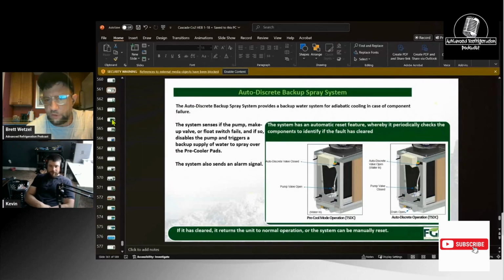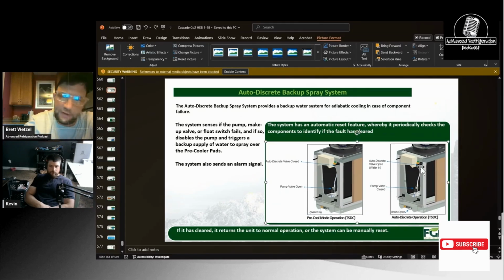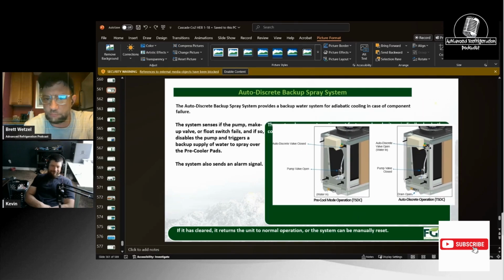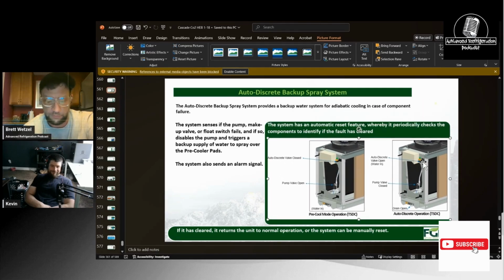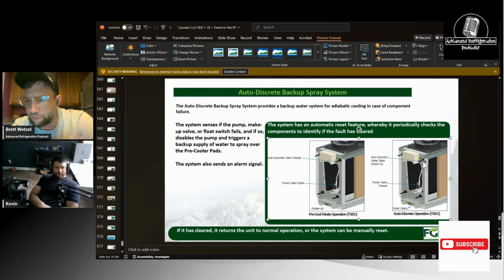like in Texas. 100%. So there's your auto discrete open valve. Up here at the top, you have the auto discrete solenoid. If it proves that there's a pump failure, there's a Belimo valve right above the pump that will close. Once it proves that the pump has failed, it'll close that Belimo valve, start feeding the solenoids at the top, and just run it and drain it out. The drain valve at that point will be open. Otherwise, right where it says auto discrete, that's where you would essentially have to hook up a garden hose if that option does not exist.